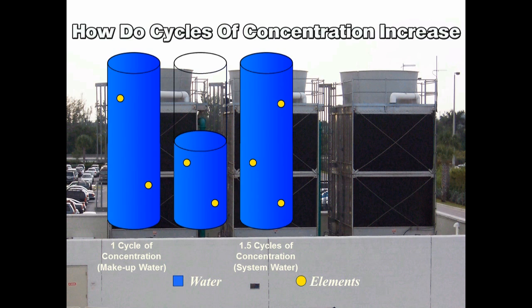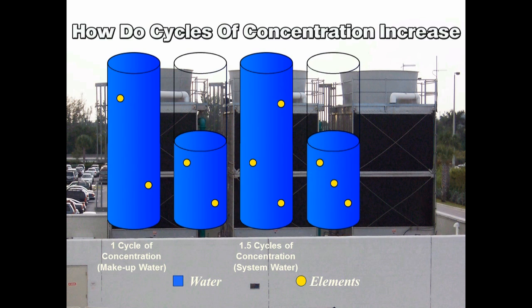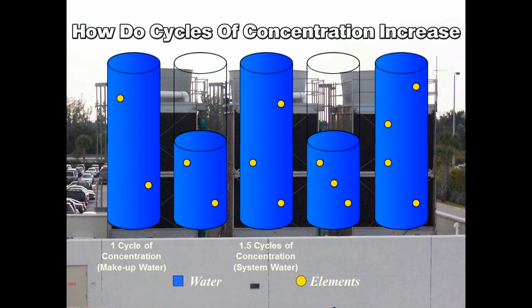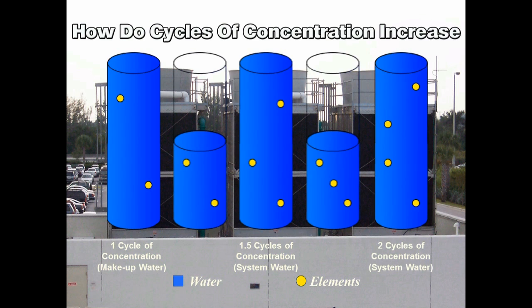If the tower evaporates half the water again and fresh water is added to replenish the loss, the elements in the tower water will have increased another 50%. The tower now has twice the elements as the incoming water, which represents two cycles of concentration.